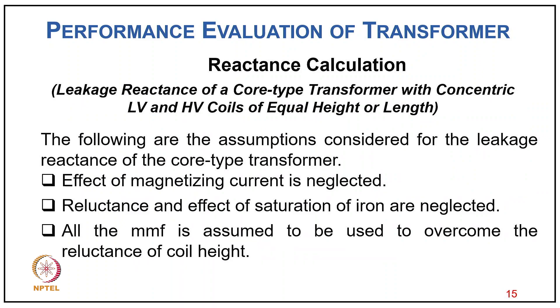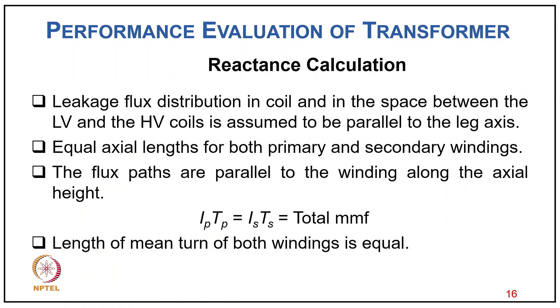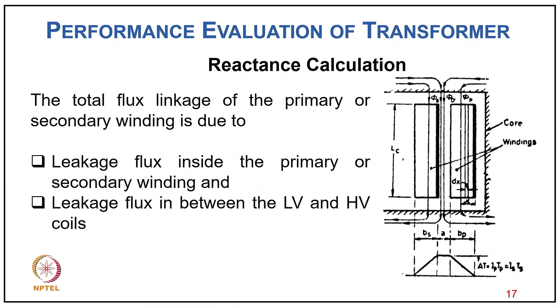The assumptions for leakage reactance calculation of a core-type transformer are: effect of magnetizing current is neglected; reluctance and effect of saturation of iron are neglected; all MMF is assumed to overcome the reluctance of the coil height. The leakage flux distribution in the coil and in the space between LV and HV coils is assumed to be parallel to the leg axis, with equal axial length for primary and secondary windings. Also, IpTp = IsTs = total MMF, and mean turn lengths of both windings are considered equal.